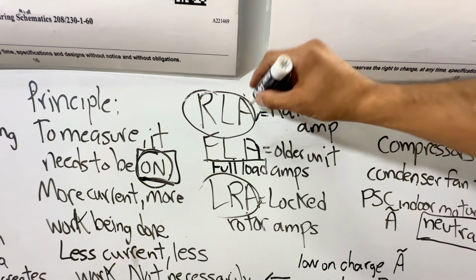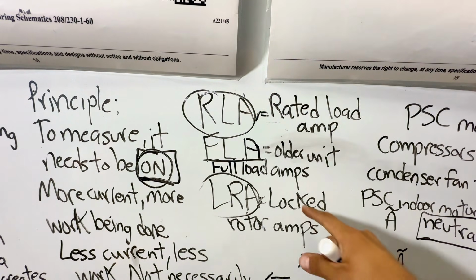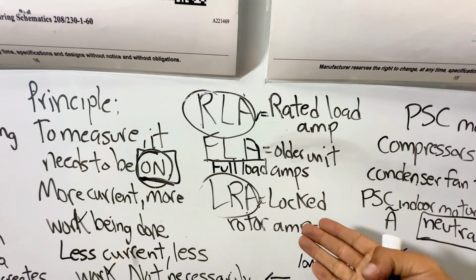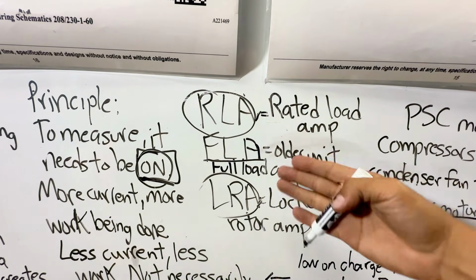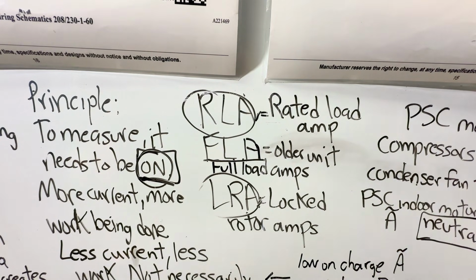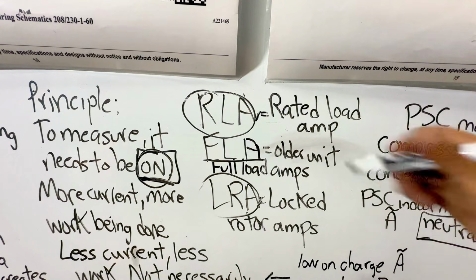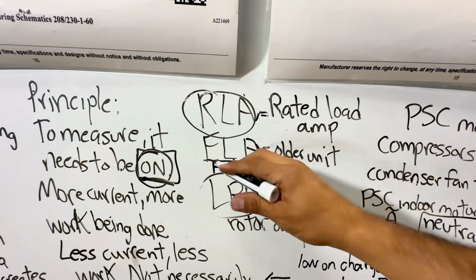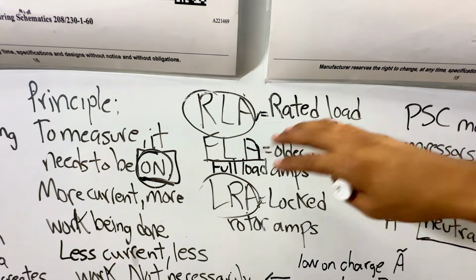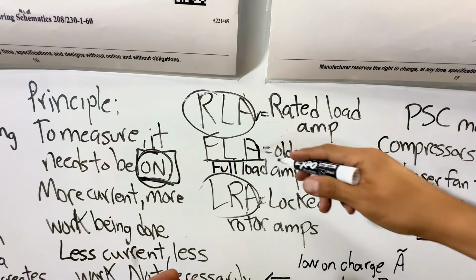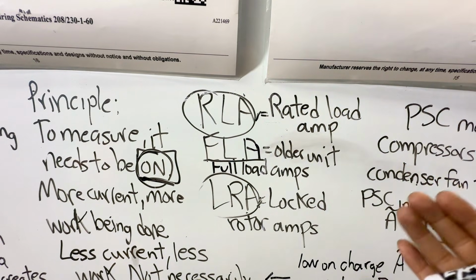So for the compressor that we're gonna check, we're gonna be checking RLA, rated load amps, and then we're gonna check the locked rotor amps. The full load amps, you will see that in this case right here, the condenser fan motor, they don't have RLA. It's full load amps, okay? And of course, there's a reason why they use full load amps on the condenser fan motors and not on the compressor. There's the science behind that.